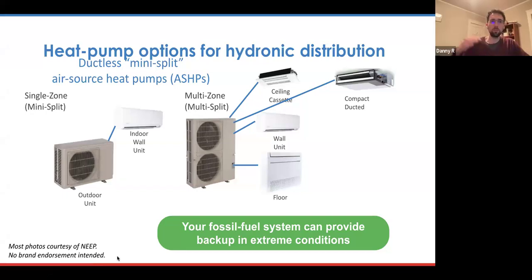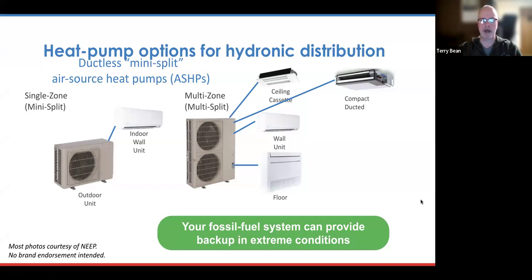So this is the additional cost Mary was referring to in her cost breakdown - the assumed cost of adding more units to distribute heating and cooling. That can be, and it's also a bit of a red flag. It's really dependent sometimes on the number of indoor units, and it's not just about the initial cost but also potentially the performance. If you have, say, six rooms and four of them are rather small, and a contractor says they'll just put an outdoor unit and six wall mounted units in, that could have performance issues in the smaller rooms. A better solution might be fewer total units, with folks willing to leave their doors largely open throughout the day. We actually have a co-worker here who does that - five rooms on his second floor, heated and cooled by two wall mounted units.